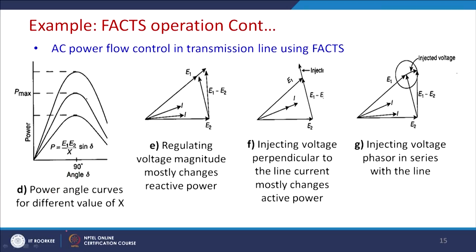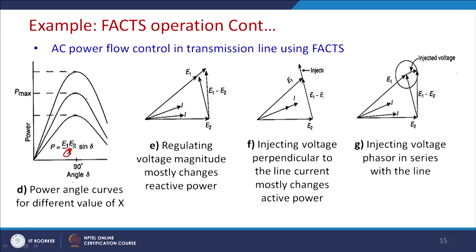If we change the value of x, we can effectively operate these lines in parallel. Increasing or decreasing the value of x changes the maximum power handling capability of the line. However, if we increase power beyond a point it may touch the thermal limit — since the voltage between points A and B is the same, what we are essentially changing is the current flowing through the line. Therefore we must dynamically consider the thermal limit when changing power.